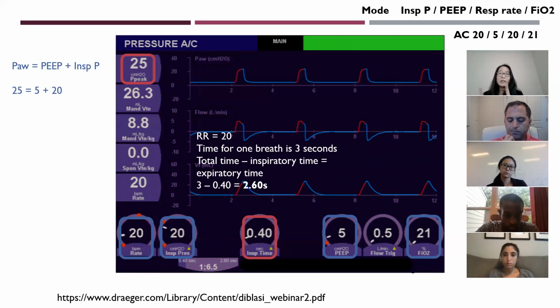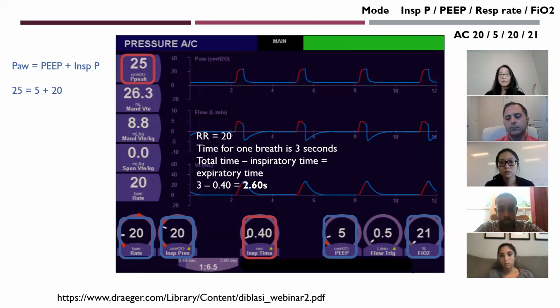So why is this important? You want to make sure that when a patient is breathing, they're fully exhaling. You want to give them ample time to move that air in and out. Because if your expiratory time is too short, for example, and then the next breath starts, that's going to lead to a lot of problems. So this is just another parameter to keep in mind and something that you can calculate. It's also here, very tiny.